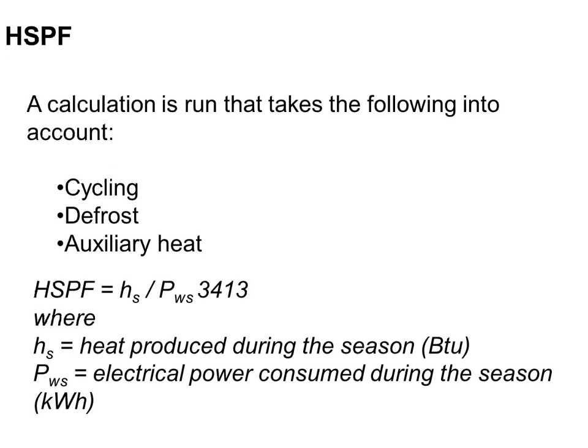So it does take into account cycling losses on the equipment. Turning things on and off are a penalty for HSPF. They're a penalty for SEER. They're a penalty for AFUE. They're a penalty for anything that cares about part load performance. All right, so cycling losses are real. The defrost cycle, which we talked about a little bit ago, is a penalty to me in terms of efficiency. And if I have to engage auxiliary heaters, that is a penalty to me for efficiency, right? So when it gets to be 10 degrees outside and I've got to bring on some electric strip heat, that's going to drop the rating of my heat pump, right? So HSPF takes all those things into account.